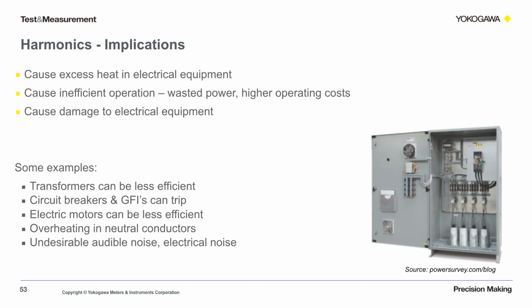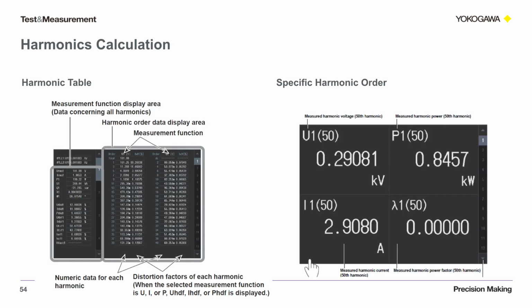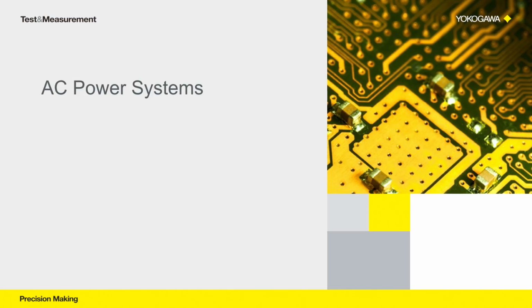To measure harmonics, luckily we have products like power analyzers and oscilloscopes to make it. This example is from the Yokogawa WT5000 power analyzer. There are many pre-programmed functions to calculate and show harmonic detail. On the left is a harmonic table. This specific power analyzer can measure up to 500 orders of harmonic content. On the right, we can isolate the specific harmonic order to see the voltage, power, current, and power factor attributed to that specific harmonic. We've covered a good amount of fundamental pieces of power.